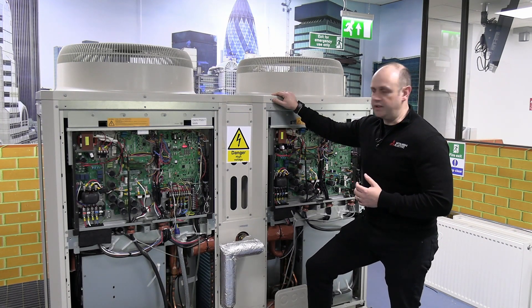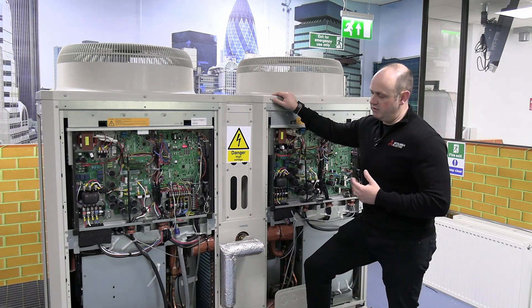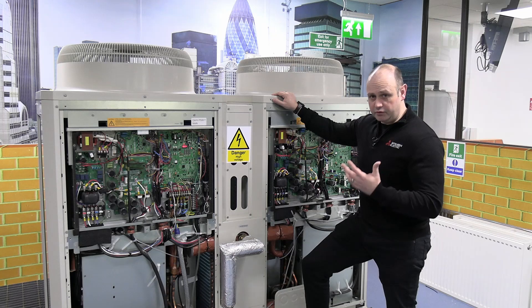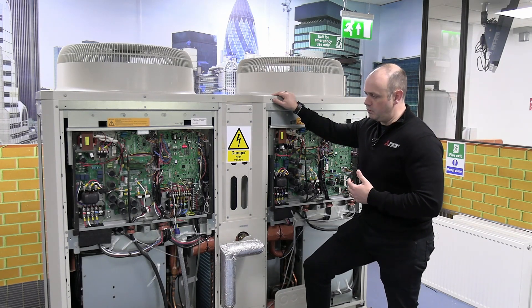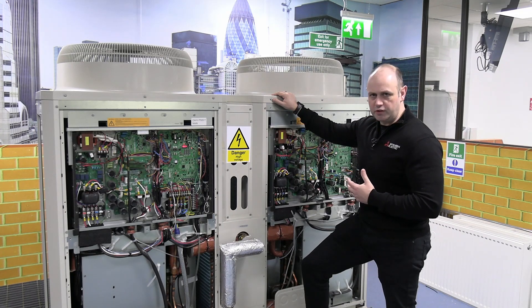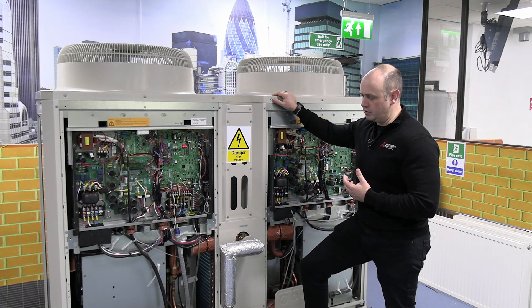What we're looking at here is a CAHV-P500Y. This is around about a 50 kilowatt heat pump system. If we're taking account for defrost and say ambient temperature — let's say we're working around zero degrees — we're probably looking at nearer to being sort of 43 kilowatts. So when we're doing our calculations, I'll be basing this around being a 43 kilowatt unit.